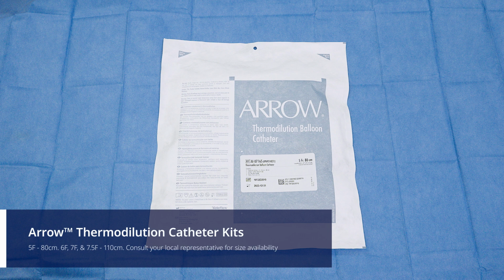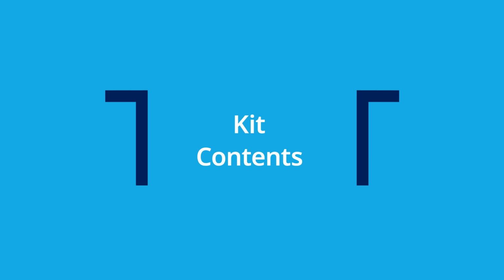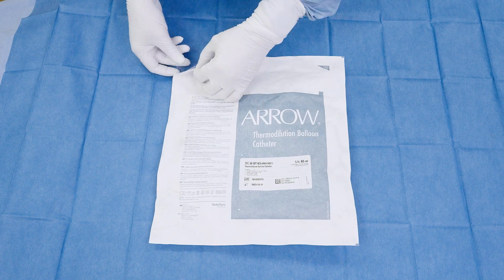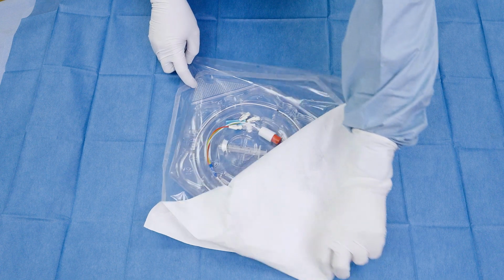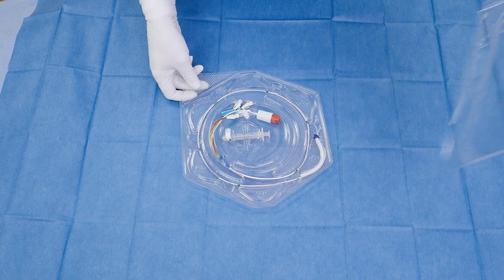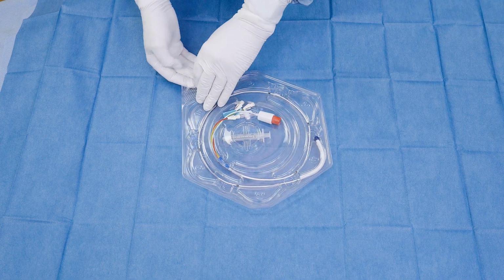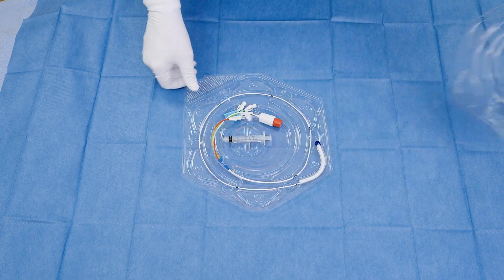Arrow thermodilution catheters are available in 5 French, 80 cm length, as well as 6 French, 7 French, and 7.5 French, which are each 110 centimeters in length. Catheter body styles range from firm for manipulation and control, to a mid-range for flexible torque control, to a softer catheter for optimal flotation.